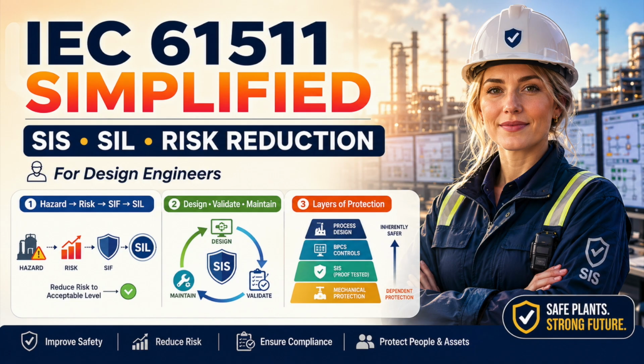A high consequence does not automatically mean a high SIL. A low consequence does not automatically mean a low SIL. The required integrity depends on the combination of consequence, initiating frequency, and the legitimate risk reduction provided by other independent layers. That word, independent, is where many safety cases become weak. You may see a control loop, an alarm, and a shutdown function represented as 3 protection layers. But if all 3 use the same transmitter, the same impulse line, the same power supply, the same communication path, or the same final element, you may not have 3 layers. You may have one failure path presented in 3 different colors on a diagram.